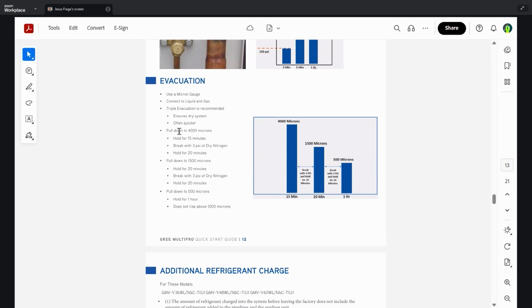So the first step is pull down to 4,000 microns, hold for 15 minutes, break with some dry nitrogen, hold for 20 minutes, pull down to 1,500 microns, hold for 20 minutes, break with 3 psi of dry nitrogen, hold for 20 minutes, then pull down to 500 microns and hold for an hour. If it does not rise above the 1,000 microns, you're good.